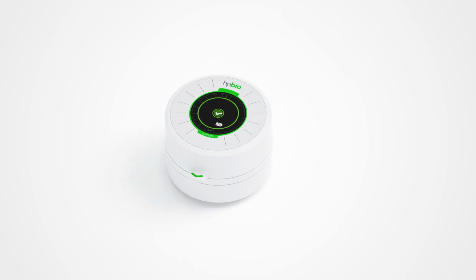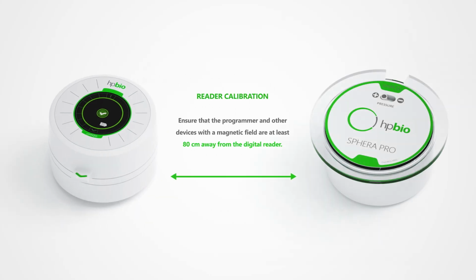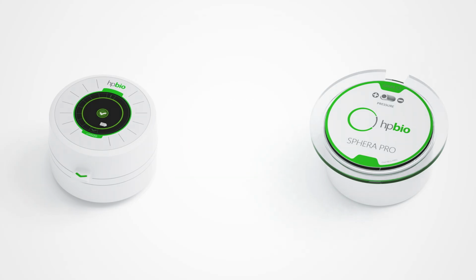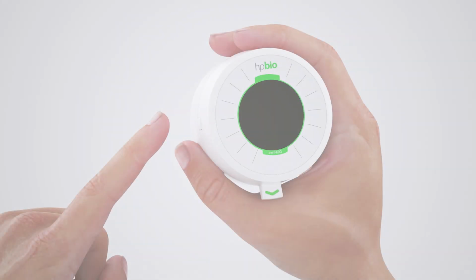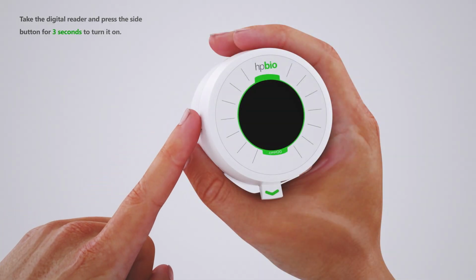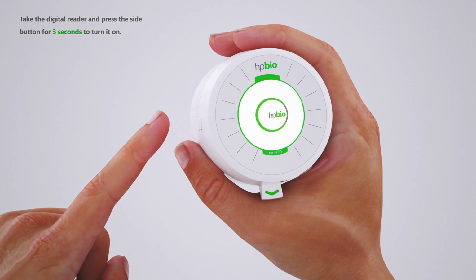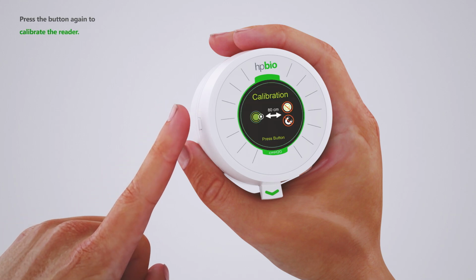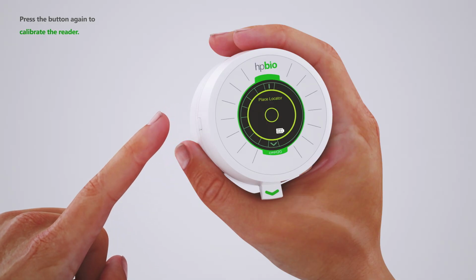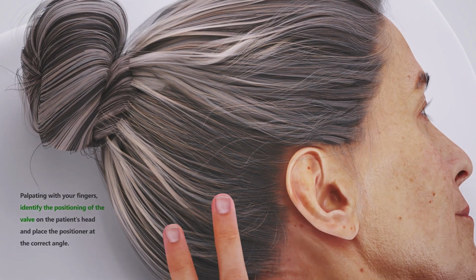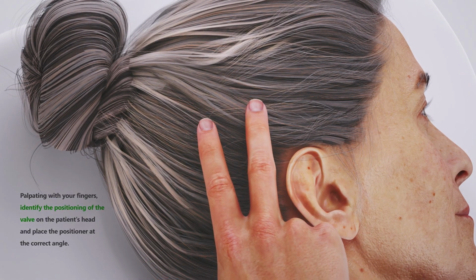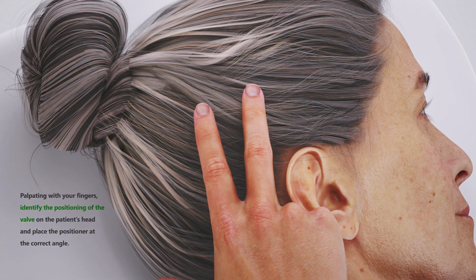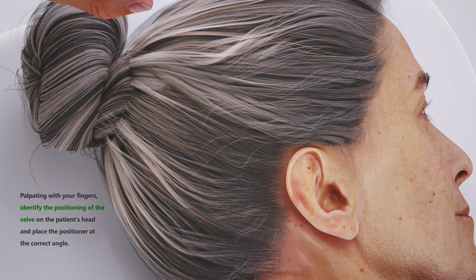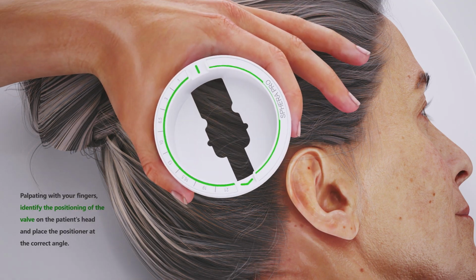Ensure that the programmer and other devices with magnetic fields are at least 80 centimeters away from the reader. Take the digital reader and press the side button for 3 seconds to turn it on. Press the button again to calibrate the reader. Using your fingers, identify the position of the valve on the patient's head, and place the positioner at the correct angle, with the flow direction arrow aligned with the path of the distal catheter.